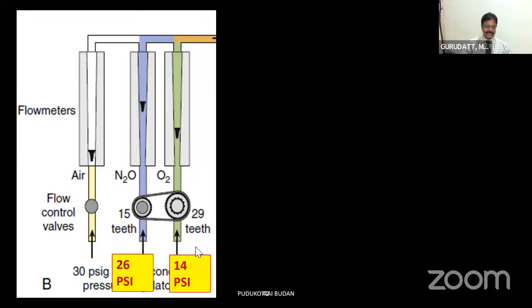But I told you that the second stage pressure regulators also reduce the pressures of oxygen to 14 and nitrous oxide to 26 psi. So again, there is a 1:2 change in the pressures of the oxygen and nitrous oxide entering here. So that completes the 3:1 ratio between the nitrous oxide and oxygen.